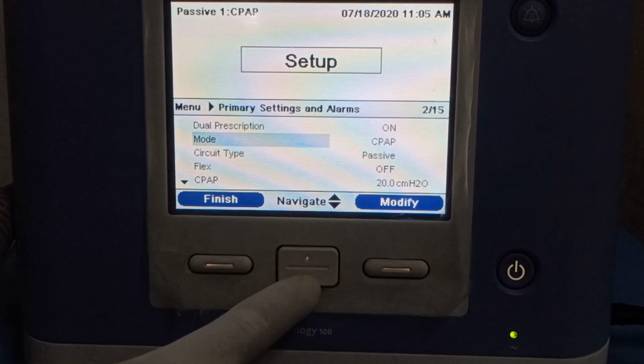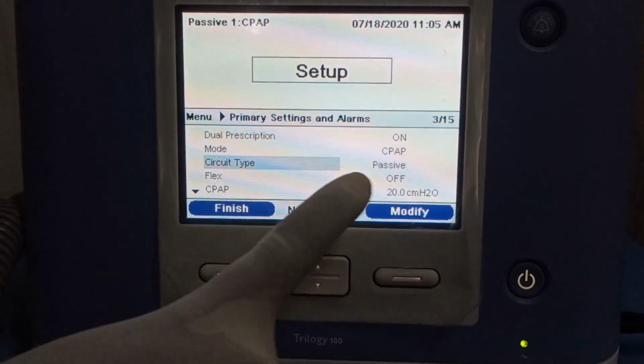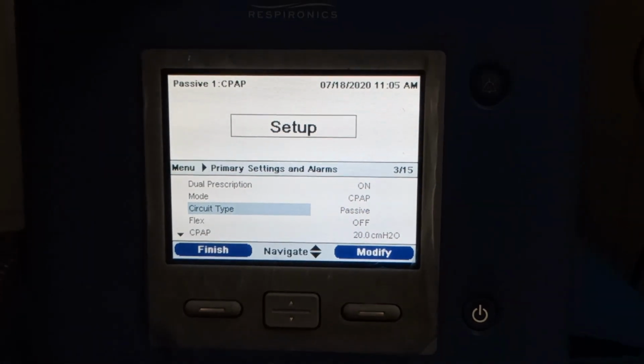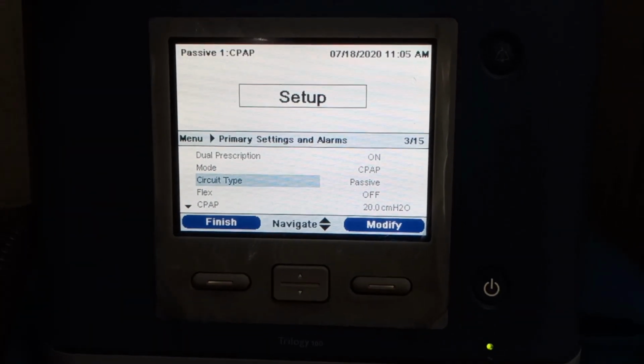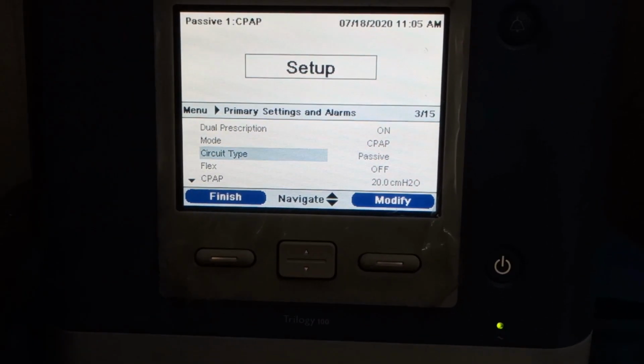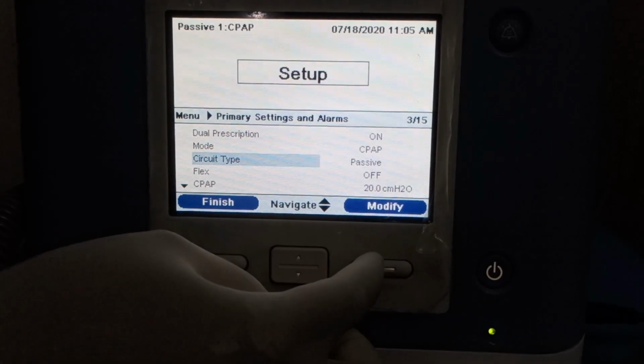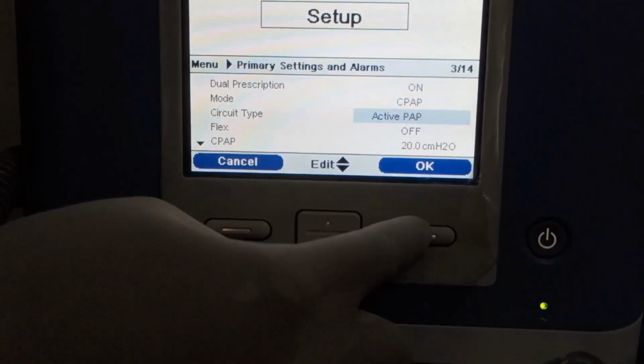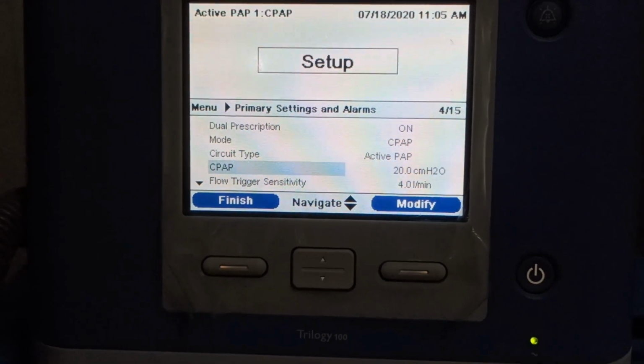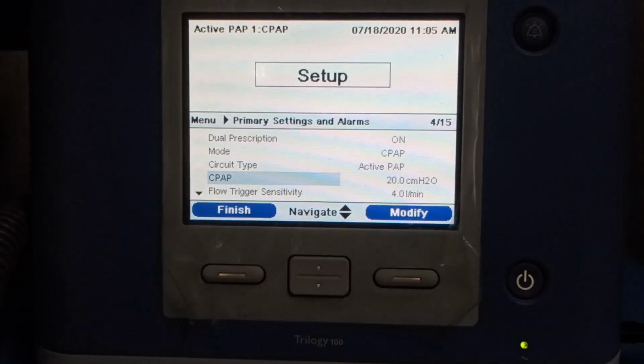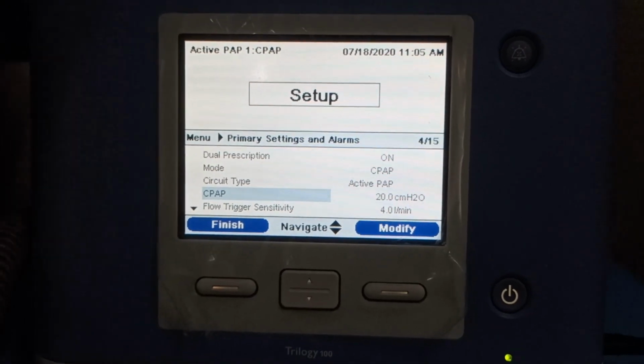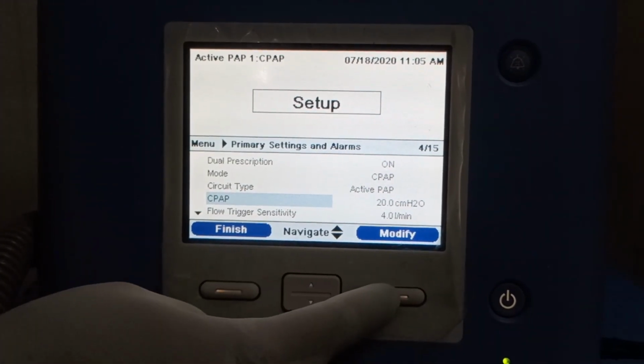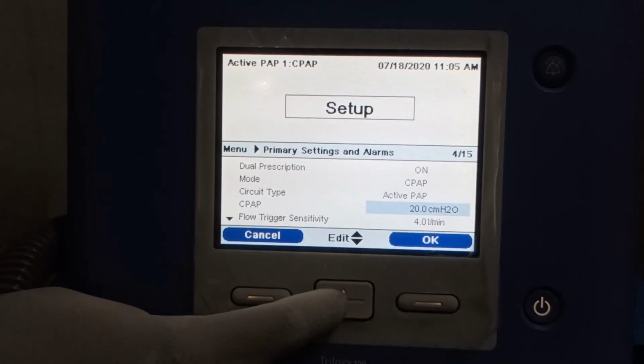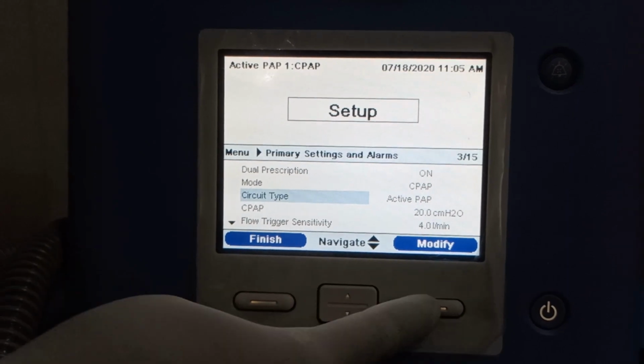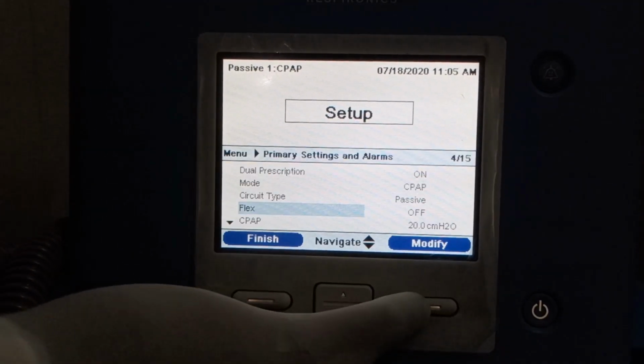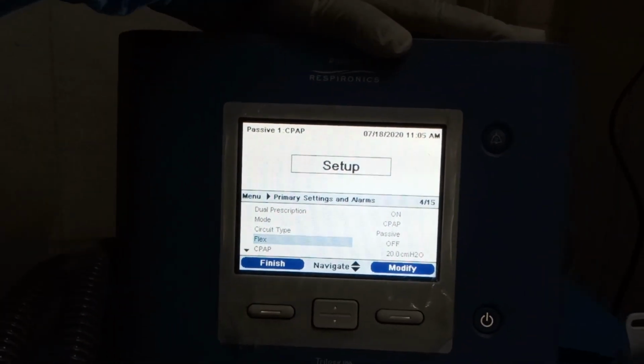Here you can see just under the mode there is the circuit type, that is passive. This system is now set up with a passive mode of ventilation. That means it can be used for now for non-invasive ventilation only. Once I modify passive to active, this is an active mode of ventilation. That means now this system is ready to use for invasive ventilation. So first we will go for non-invasive ventilation, so I will change the circuit type back to passive. Now the system is set to a passive circuit type of ventilation.